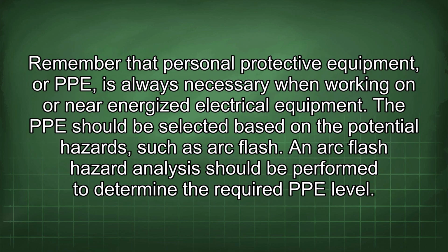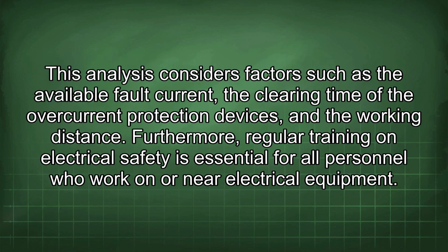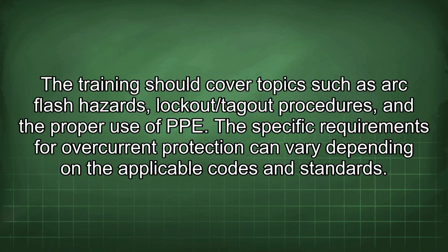Remember that personal protective equipment, or PPE, is always necessary when working on or near energized electrical equipment. The PPE should be selected based on the potential hazards, such as arc flash. An arc flash hazard analysis should be performed to determine the required PPE level. This analysis considers factors such as the available fault current, the clearing time of the overcurrent protection devices, and the working distance. Furthermore, regular training on electrical safety is essential for all personnel who work on or near electrical equipment. The training should cover topics such as arc flash hazards, lockout/tagout procedures, and the proper use of PPE.